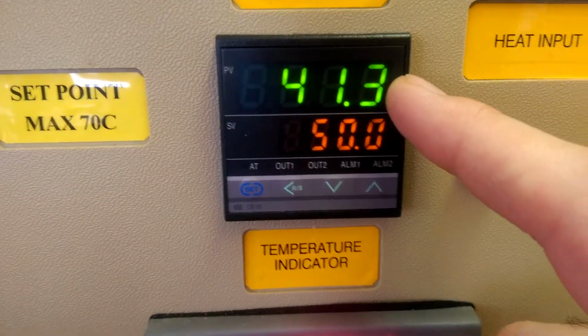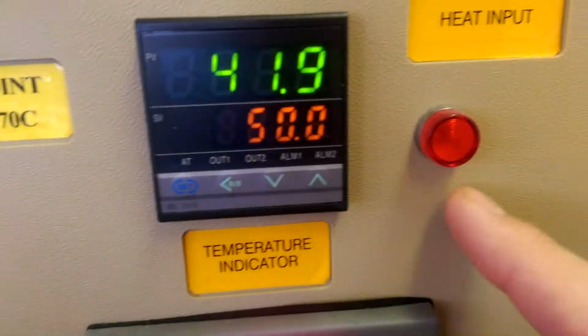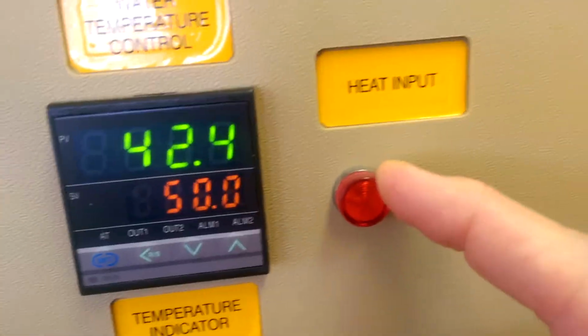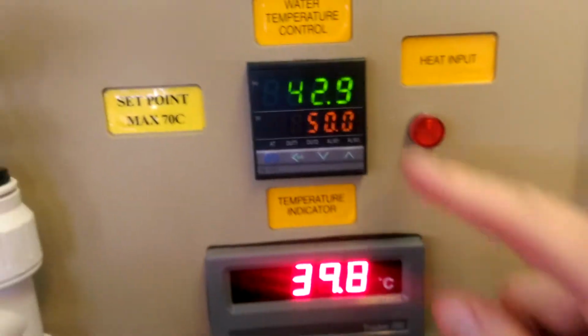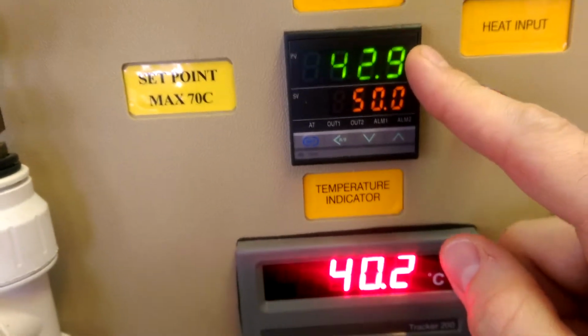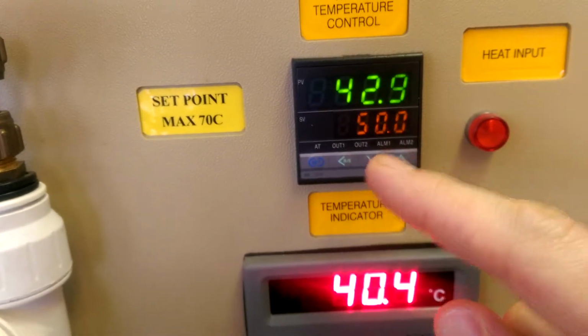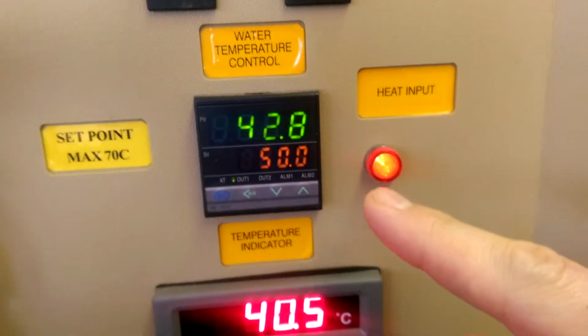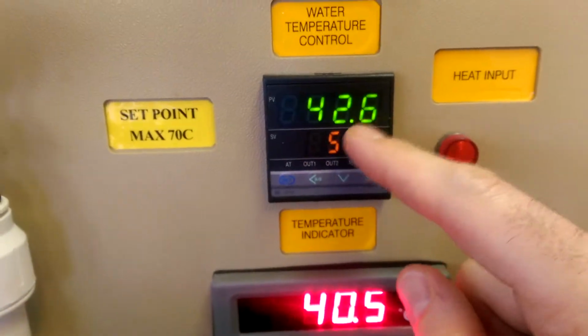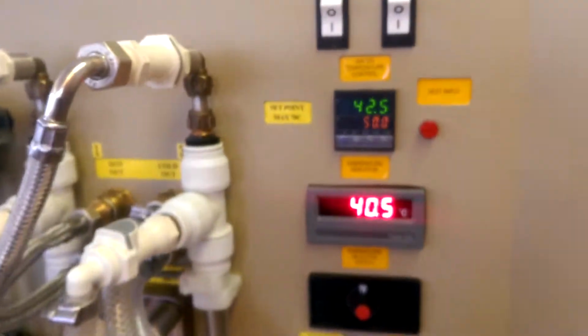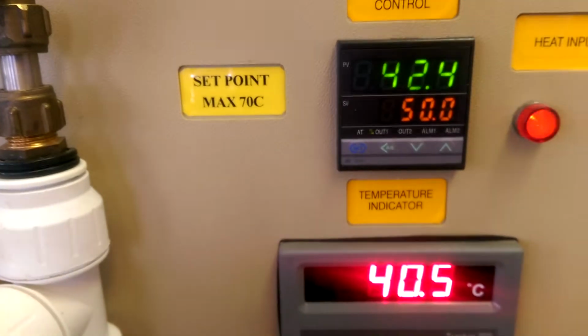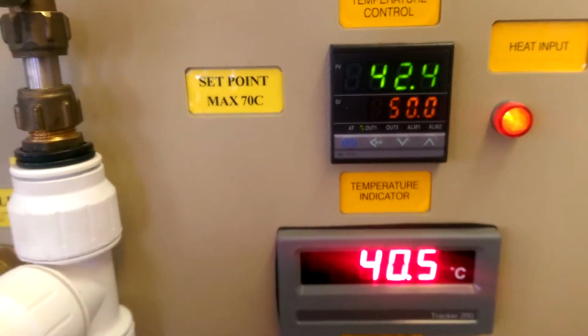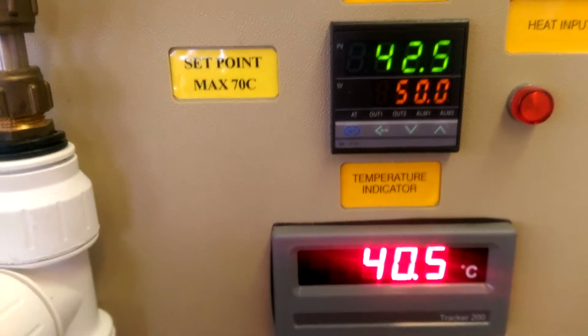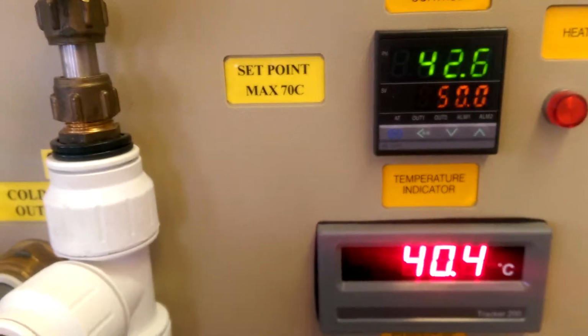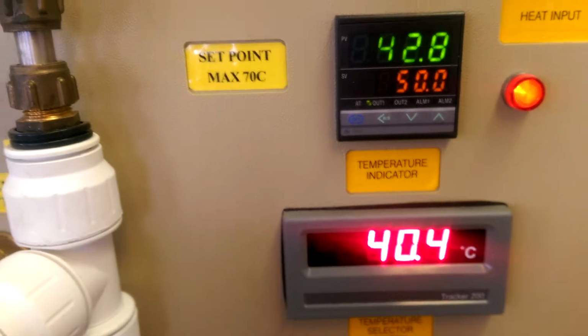So what's going to happen is that this is controlled by a PID controller, and the heater is turning on and off, regulating the water temperature by turning on and off. So you're going to see this temperature rise probably above 50. It'll probably go to 52, then down to 49, then up to 51, and eventually level off. When you first turn on the unit, it could take up to about 7 minutes to level off. But once the unit has leveled off, any time you make a change, whether it's to flow rate or to configuration, it should only take a few minutes to regulate.